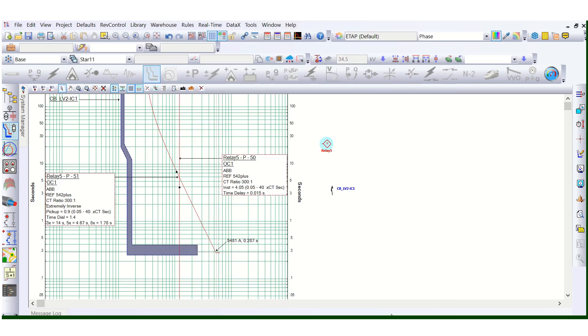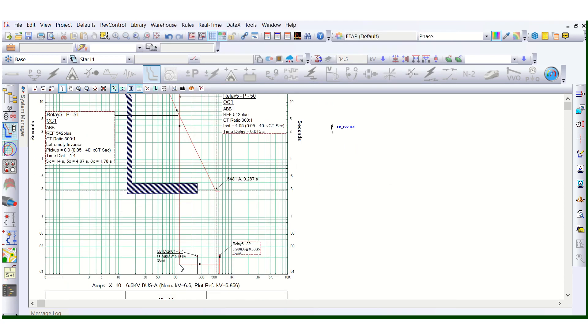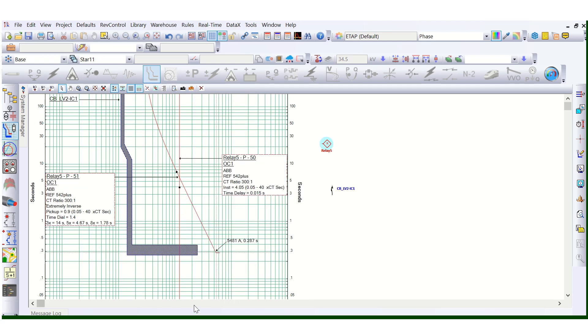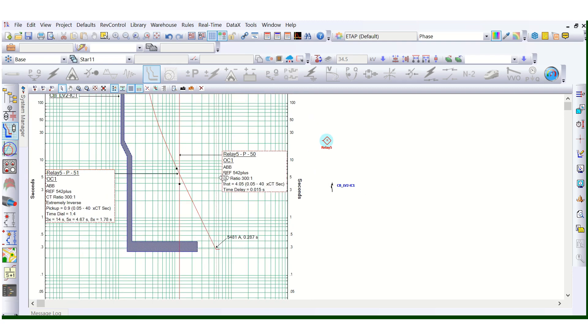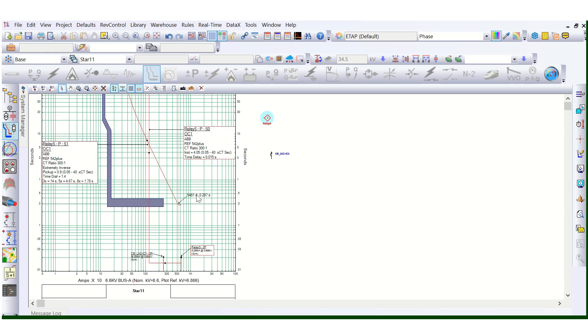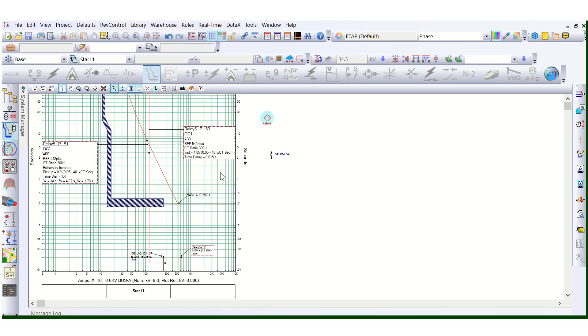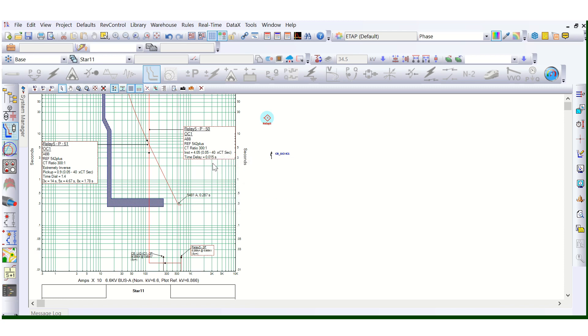If I put 0.015, this curve comes down — this is instantaneous. This is called the instantaneous setting where the time delay is 0.015 seconds, meaning there is no intentional time delay. The minimum time the relay will take to pick up for the instantaneous setting is 15 milliseconds. In some cases this is 0.05 or 0.02 — for this particular relay it is 15 milliseconds, that means 0.015 seconds. This is the 50 setting.